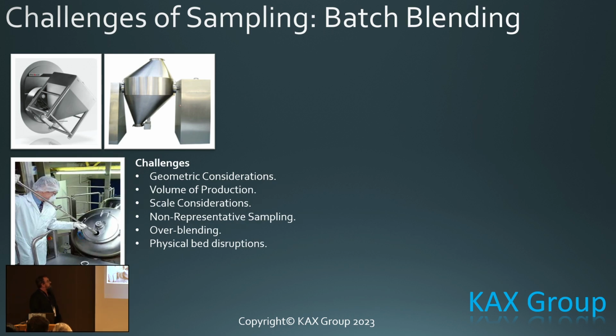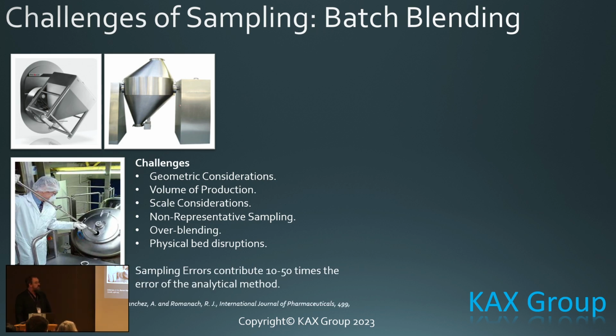We've also heard about the challenges of thief sampling. As Manel said this morning, thief sampling is a no-no because it contributes up to 50% or 50 times the analytical error. The sampling error is 50 times greater than the actual analytical error of the PAT instrument. So the challenges that we have, even before we start, we've got geometrical considerations, volume of production, scale considerations, non-representative sampling, over-blending, physical disruptions, and as I said, along with my good colleague Kim Isbenson, if I didn't say this, he'd whip me, okay, that we need to look at a representative sampling situation.